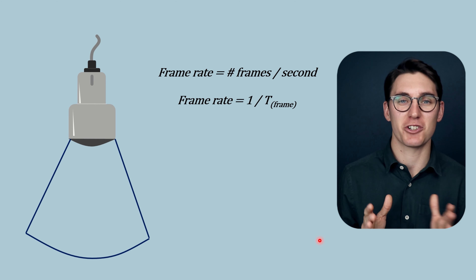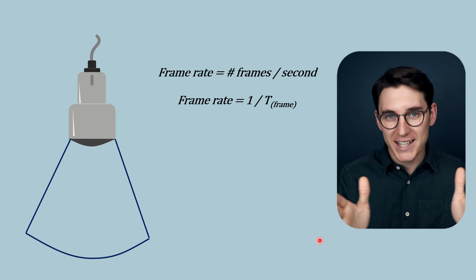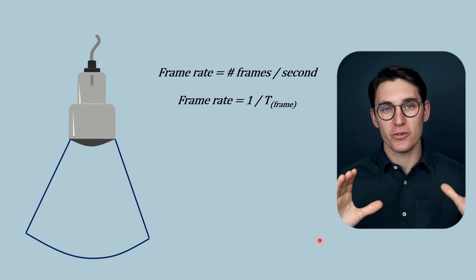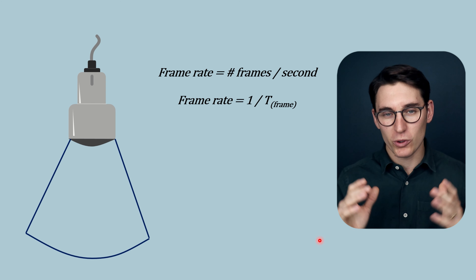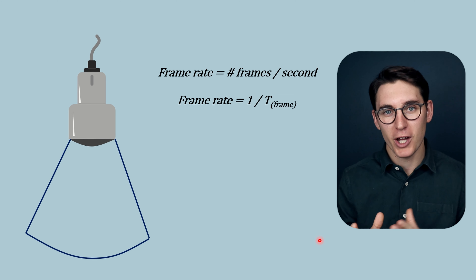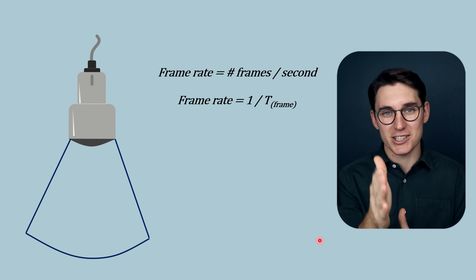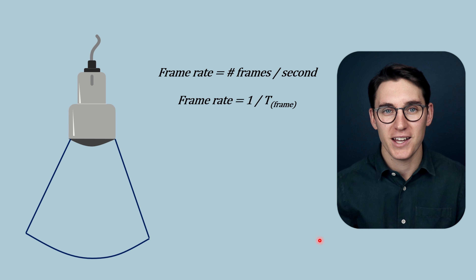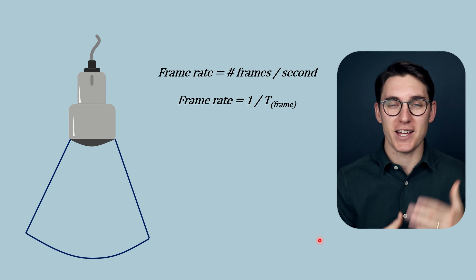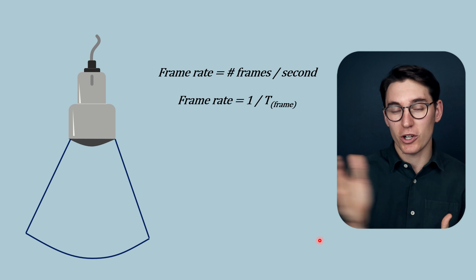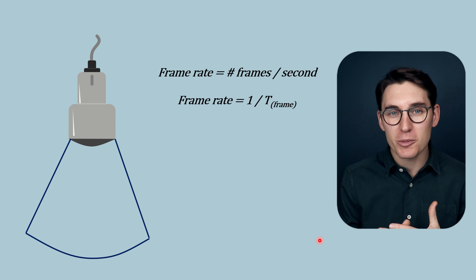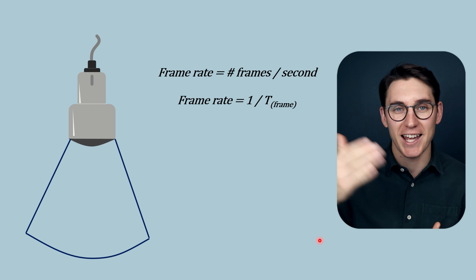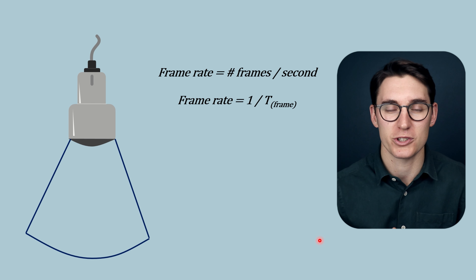When creating an ultrasound image, the ultrasound probe projects a field of view into the tissue being scanned. This field of view represents what's known as a frame. To create one B-mode frame, multiple A-lines of data have been acquired and stitched together to create that single frame. Multiple frames played one after another in quick succession give us what looks like a moving image. At a certain point, when frames are played quickly enough, we won't be able to tell we are seeing individual frames.